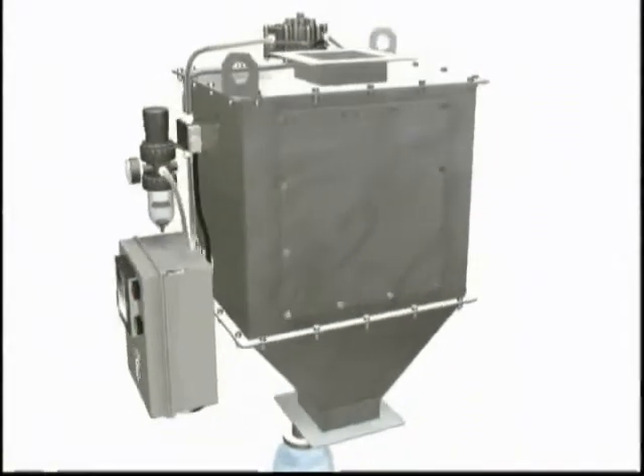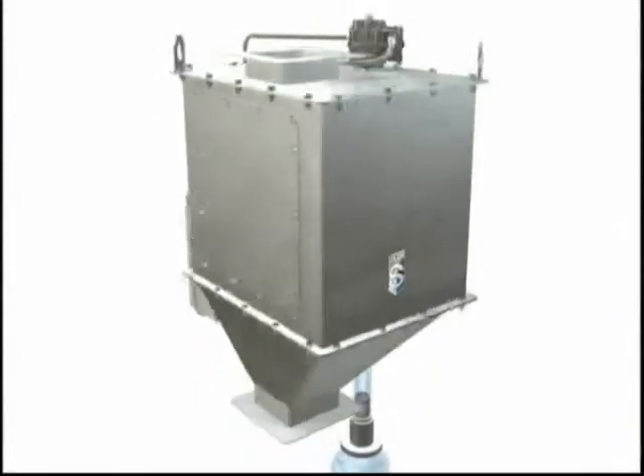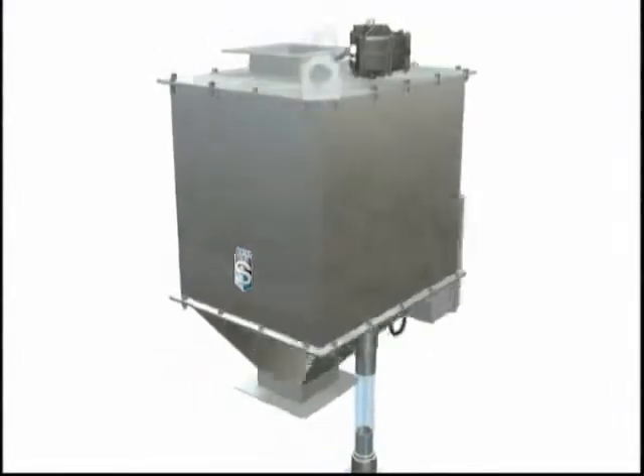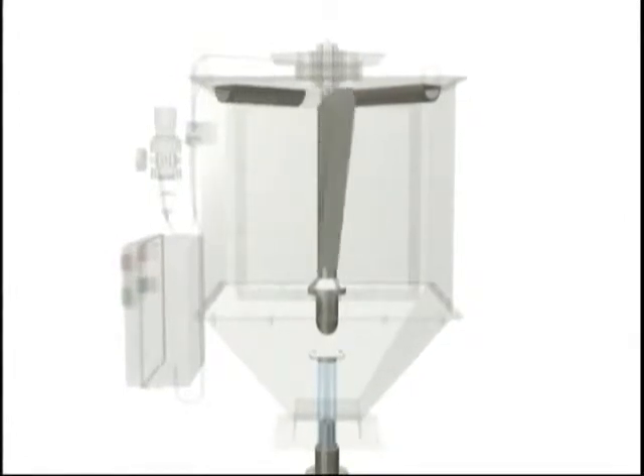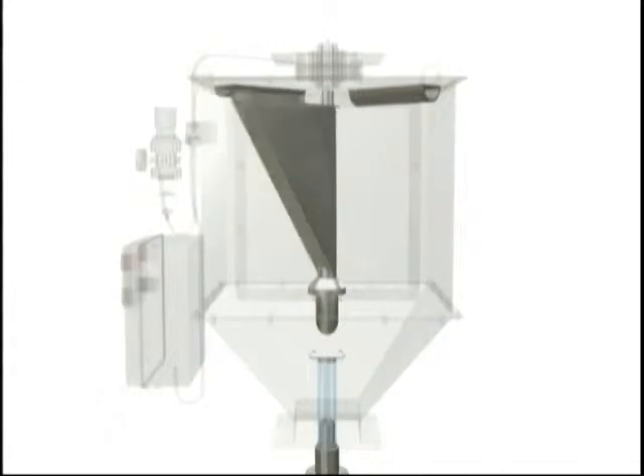The Model SA samples when a solenoid-controlled pneumatic rotary actuator swings a pelican-type diverter on an arc across the entire product flow. The diverter captures the sample then discharges it through the pelican tube.